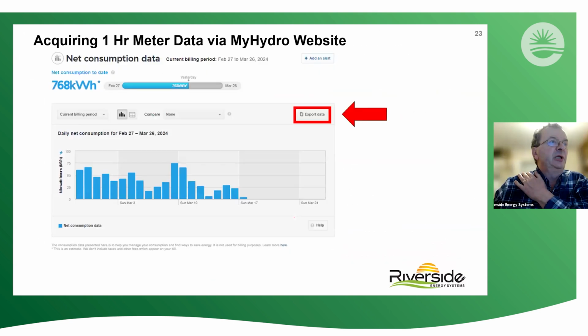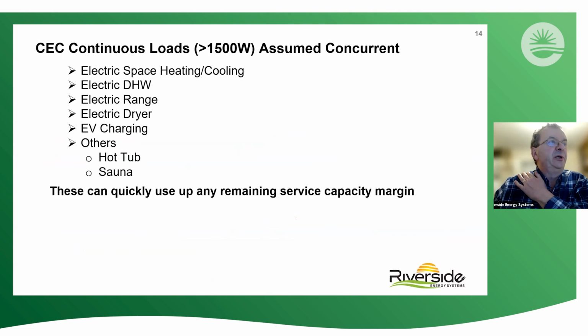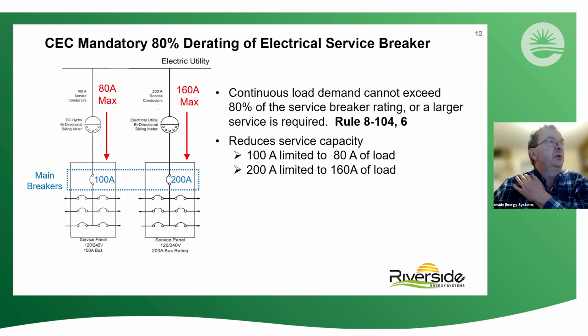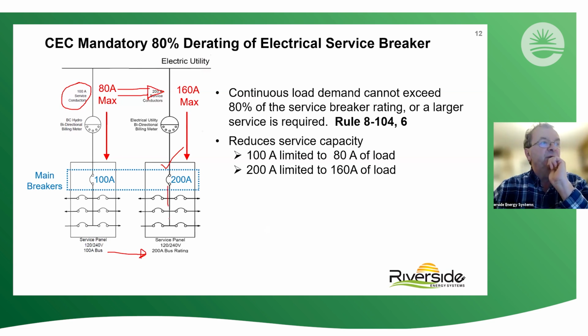Oh, yeah. Yes, absolutely. So let me go back to a slide here. Let's suppose we look at this example. There's a 100 amp service on the left, so these 100 amp service conductors are the limit. If we upsize our service so that we have 200 amp service conductors, then we also have to upsize the panel to take advantage of that. The new panel would have 200 amp or higher buses, and it would have a 200 amp main breaker. So if we're upsizing the service, it will almost always mean upsizing the panel as well, unless somebody installed an oversized panel to begin with and had a smaller main breaker to accommodate.